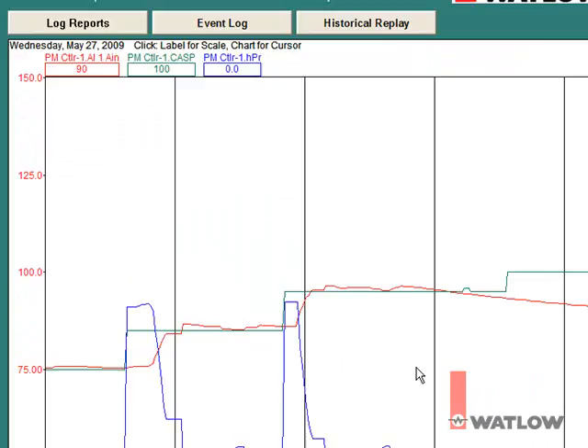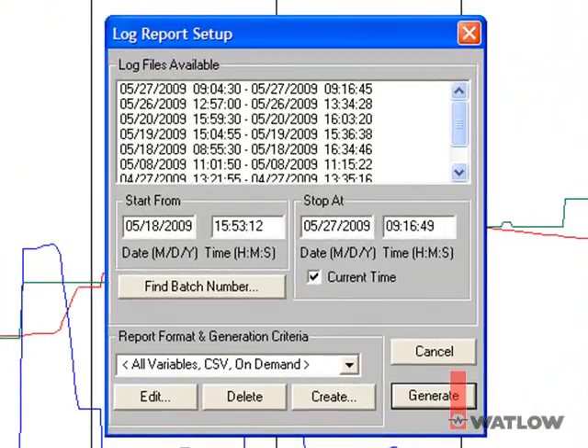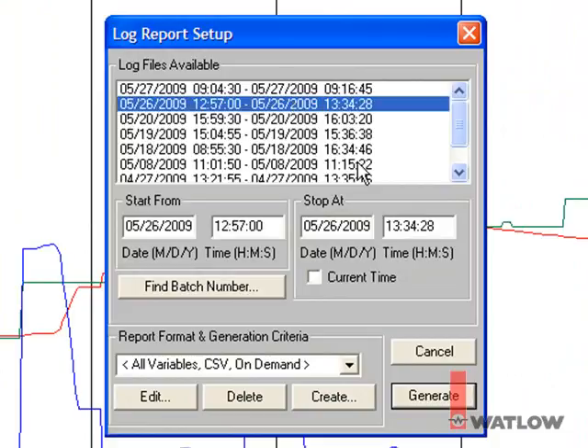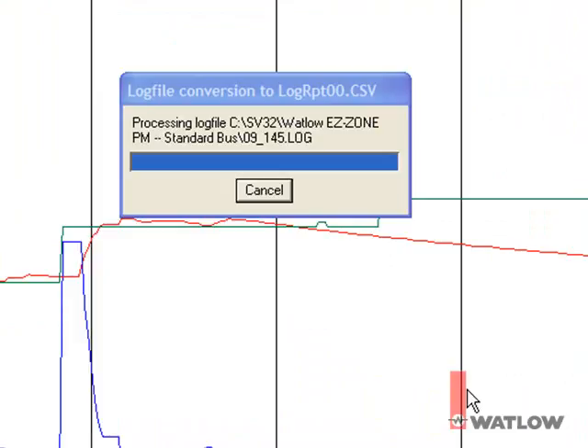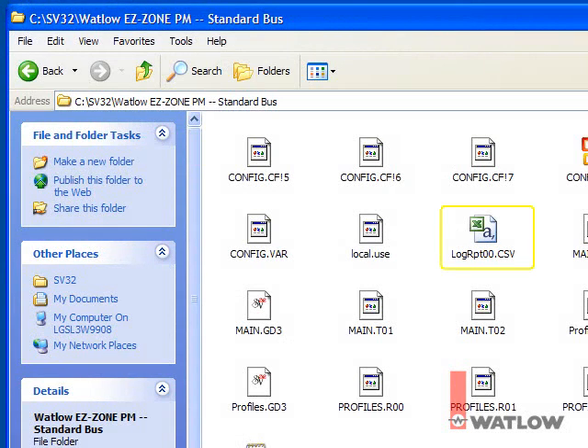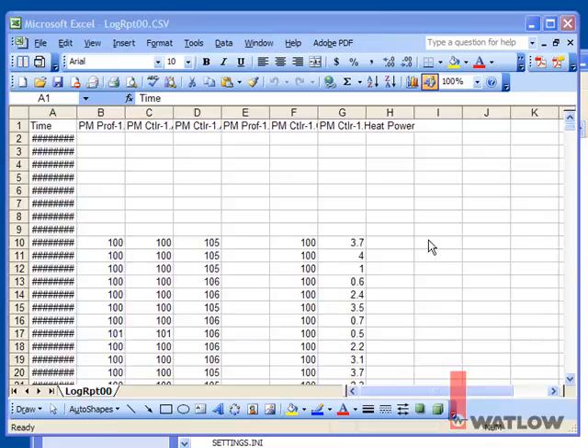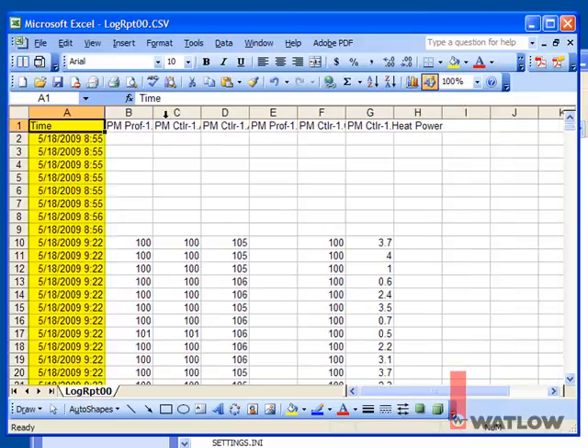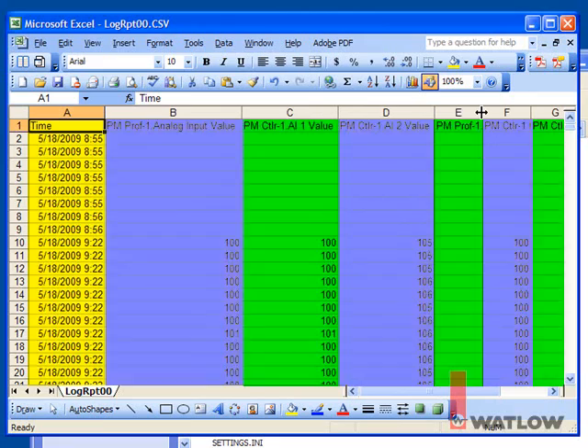To export a data log report that can be used in other programs such as Microsoft Excel, click the Log Reports button. Select one of the date and time ranges during which data was recorded, then click Generate to output the report. By default, the data is exported to a file named LogRpt, the two digit serial number, dot csv. This file is located in the configuration folder under the SpecView program folder — normally C:\sv32. The configuration folder in this case is Watlow Easy Zone PM Standard Bus. When you open the file in Microsoft Excel, you see it has a column with dates and times, and an additional column for each variable that is logged. The file contains a row for each set of time stamped data points.